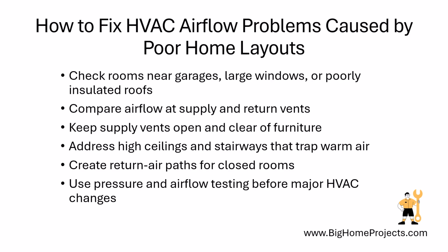A useful test is to close all exterior doors and windows, then hold a thin tissue near each supply and return vent to compare airflow. Check rooms at the same time because different temperatures throughout the day may point to sunlight or insulation rather than equipment failure. Keep supply vents open and avoid blocking them with furniture, curtains, or rugs.